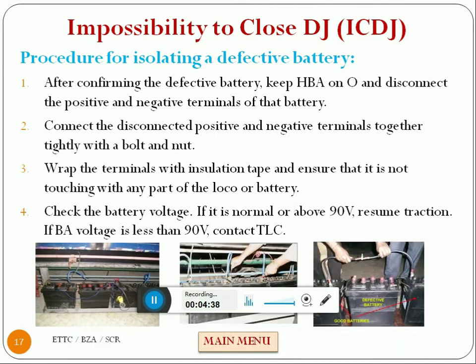We have to check the 80 elements of the batteries one by one, keeping HB on one position and ZCP on. Find out the defective battery. After finding the defective battery, keep HB on 0. Disconnect the positive and negative cables of the defective battery.